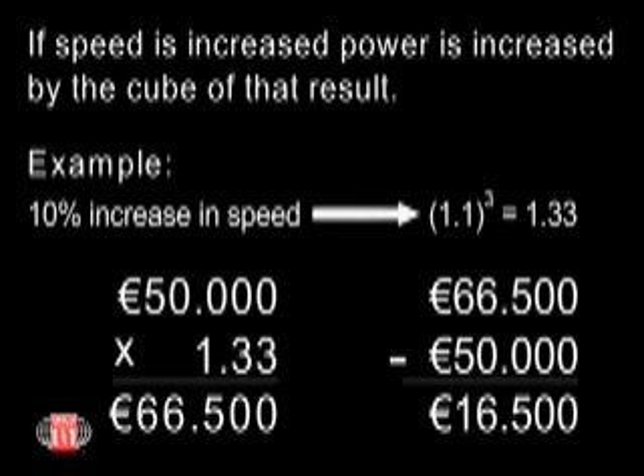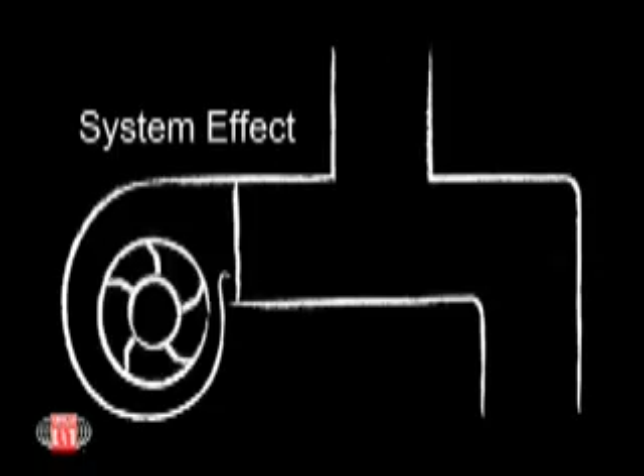Or consider a second example of a 75 kilowatt fan that costs 50,000 euros per year to operate. A 10% increase in speed to compensate for system effect will result in an over 16,000 euros operating cost increase per year. And that's just for one fan. In addition to cost increases, there are other real dangers to be considered before simply increasing the speed of a fan to overcome system effect.